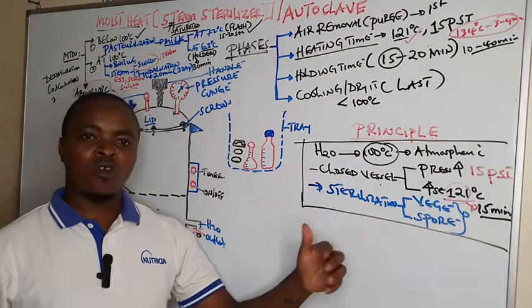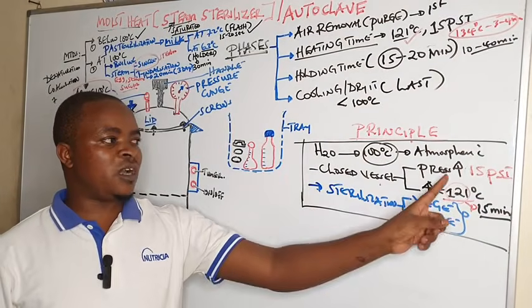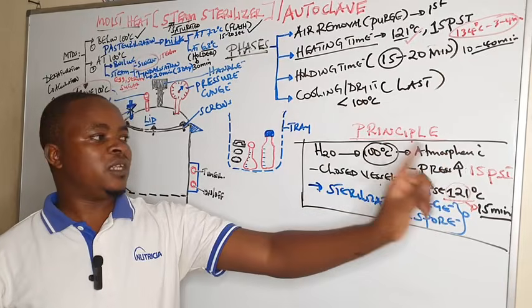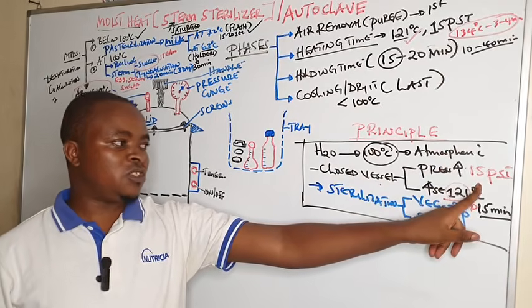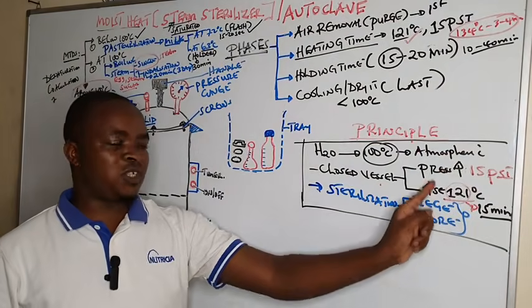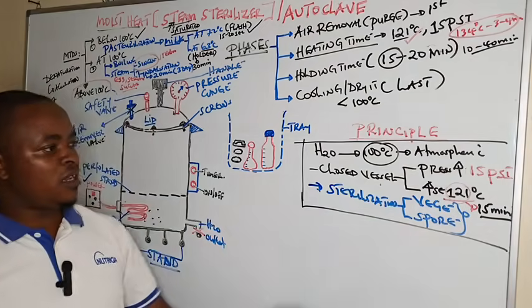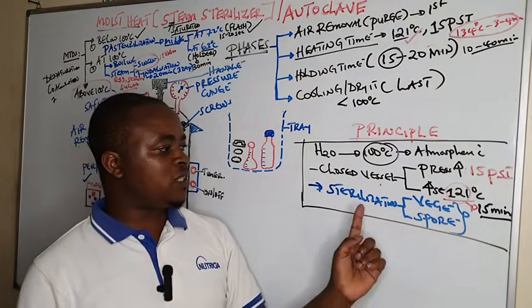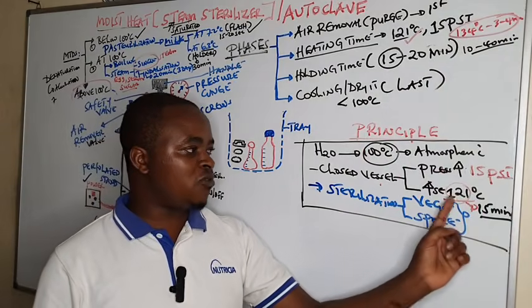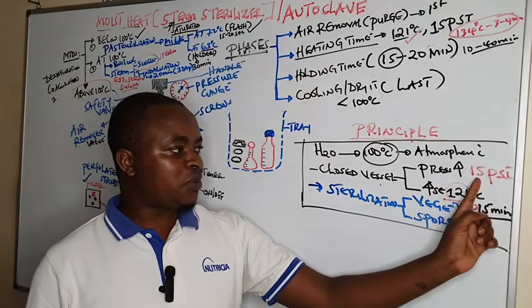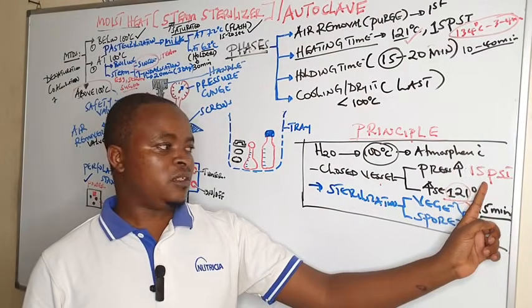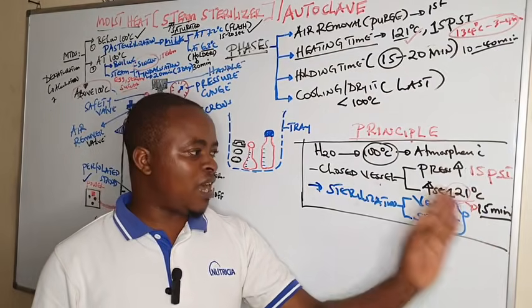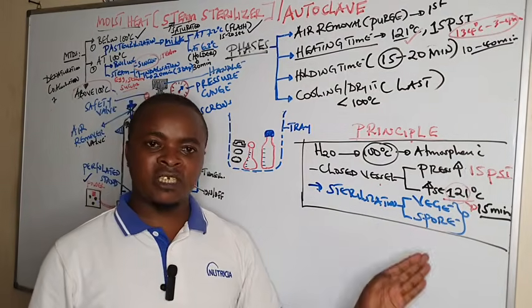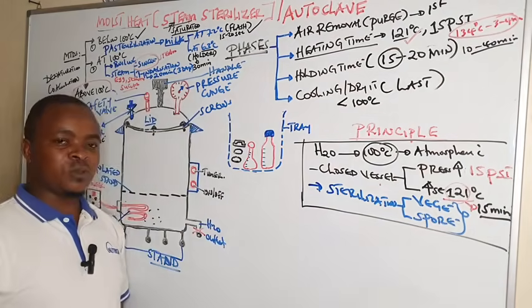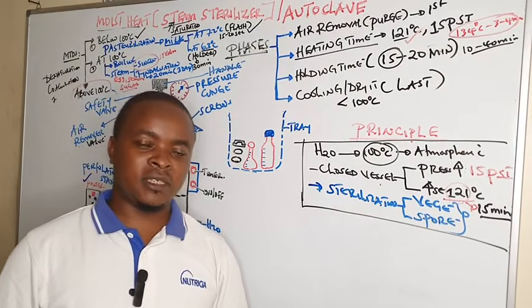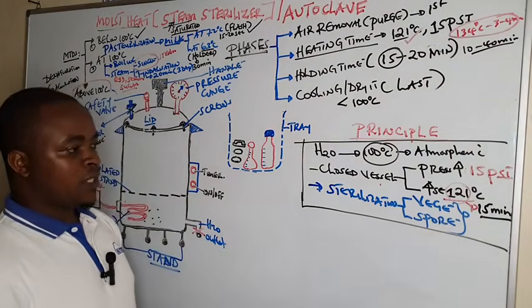But in a closed vessel, the pressure increases above atmospheric pressure, that is at 15 pounds per square inch. Also, when pressure increases, it leads to an increase in temperature above 100, that is at 121. So if we load materials and we sterilize at 121 degrees centigrade at a pressure of 15 psi for 15 minutes, it is enough exposure time to kill both the vegetative and spore-forming organisms, achieving complete sterilization. That is what we can discuss.